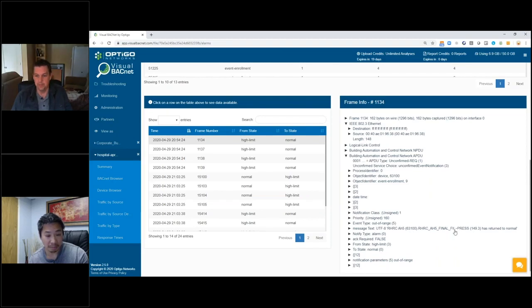So this looks like a filter alarm based on pressure. So something here is probably alarming. The alarm value is a little tight, and it could just be reduced. Or maybe it needs a lockout, something similar to that.